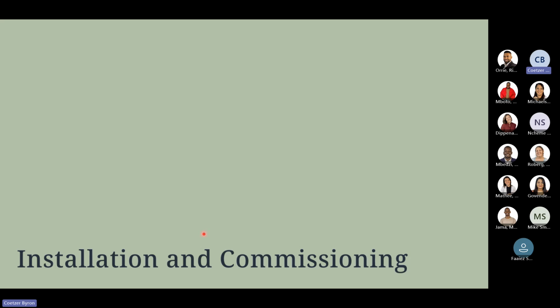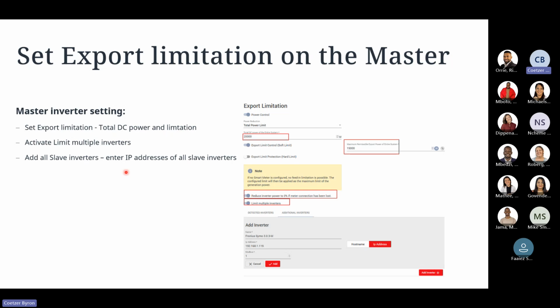For the installation and commissioning of this feature, we need to make sure that we set the export limitation on the master inverter. You can set this as a soft limit because we are using multiple inverters. We'll need to set the total DC power for the system, and then add all slave inverters by entering their IP addresses. Under the network connection, we enter the IP address that we've assigned. Typically we say use dynamic, but you can use a static IP.